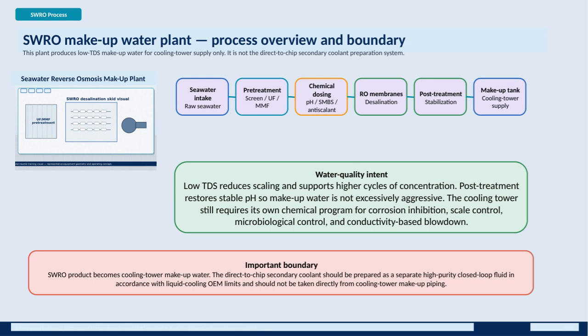The heart of the system is the reverse osmosis membranes, which perform the desalination process, removing salts and impurities to produce low TDS water. Post-treatment is then applied to stabilize the water's pH, ensuring it's not too aggressive or corrosive for the cooling tower system. The treated water is stored in a makeup tank and supplied to the cooling tower. The goal here is to reduce scaling and support higher cycles of concentration, which improves efficiency.